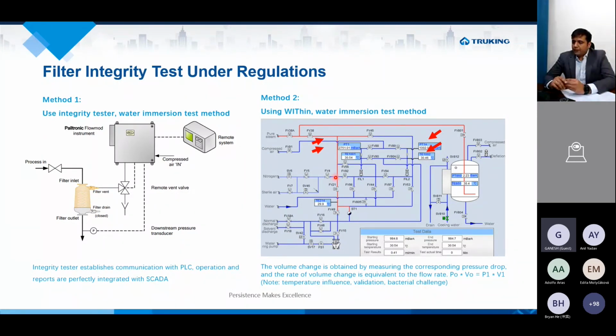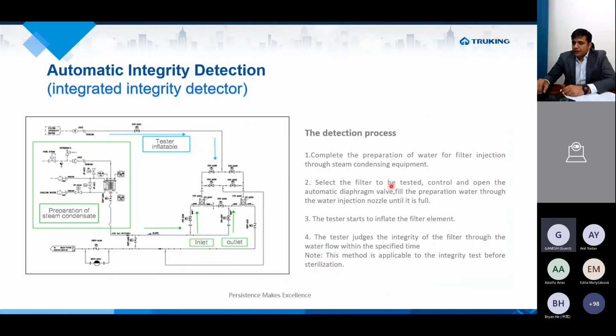So these are the lines that are being used for the pressure: compressed air and pure steam being connected to the filters. And that is how we are conducting the test in this particular area. We'll also have more slides for the WIT test at a later stage. So first of all, the detection process, which is common for both: the complete preparation of water for filter injection through the steam condensing equipment is done. Select the filter to be tested, control and open the automatic diaphragm valves, and fill the preparation water through the water injection nozzles until it is full.